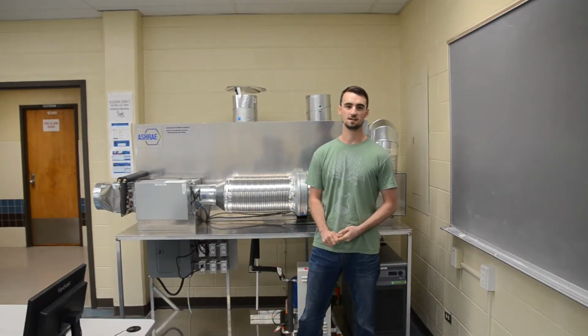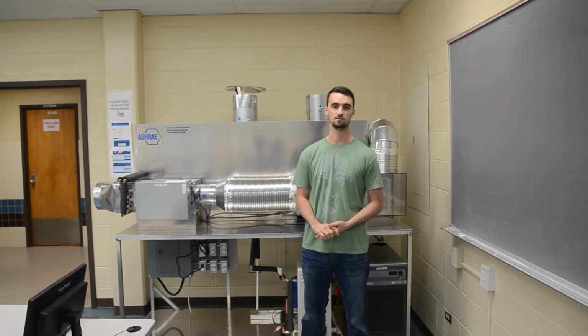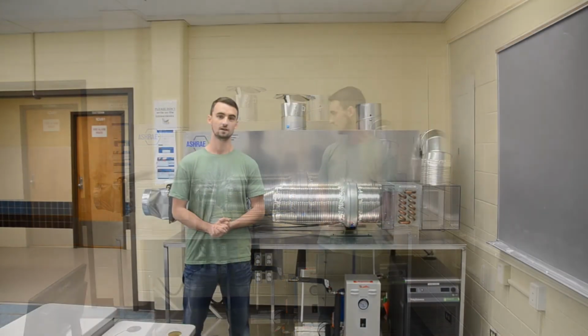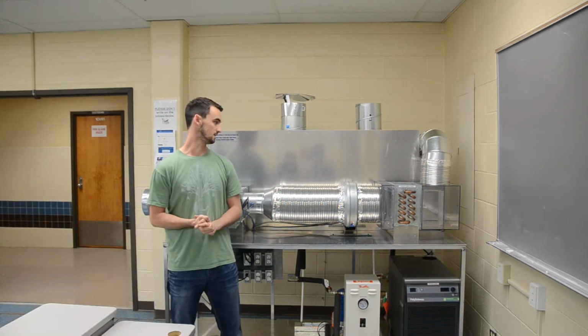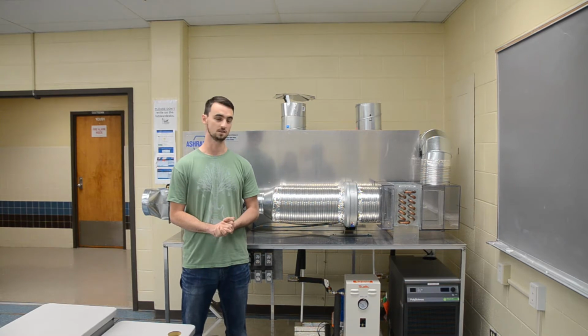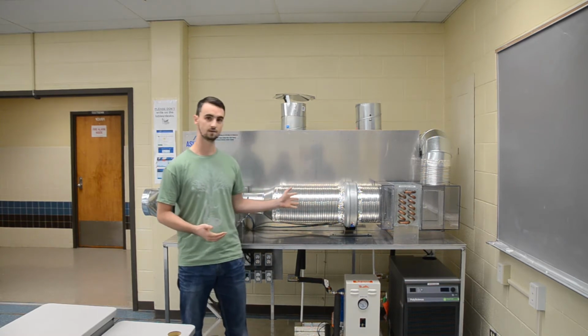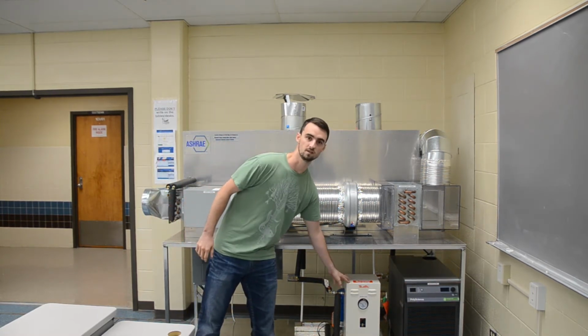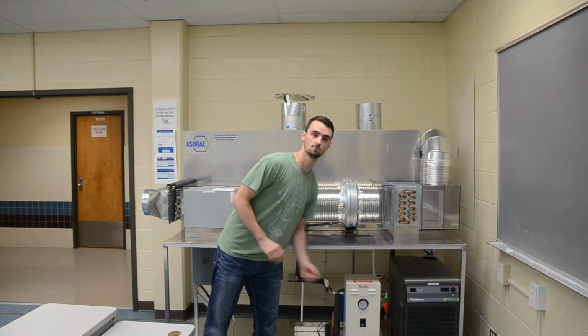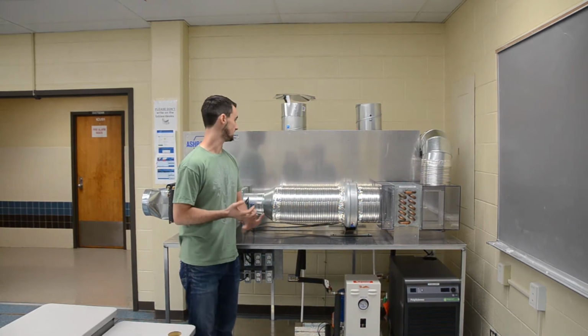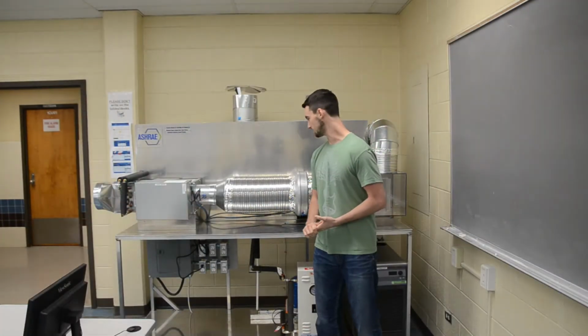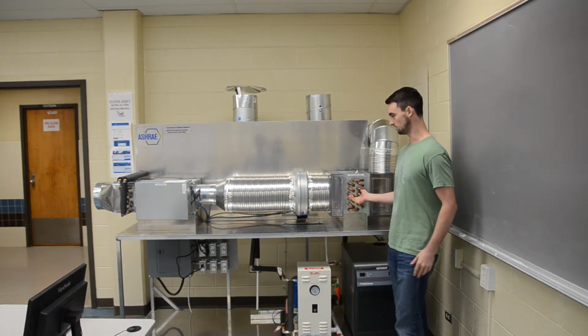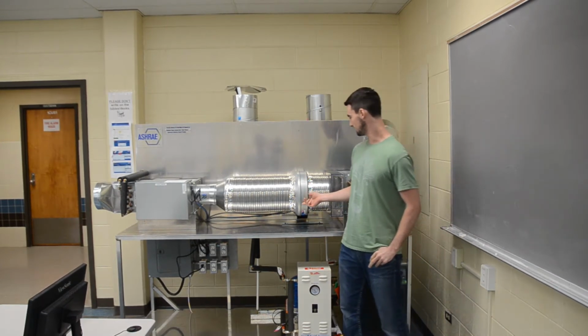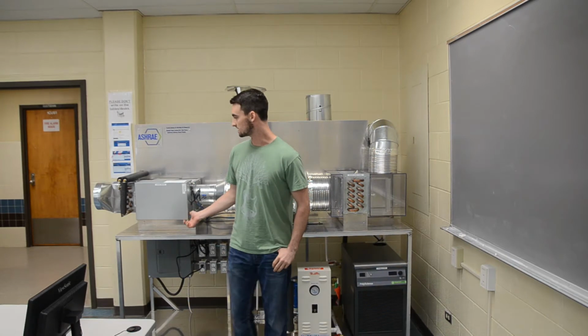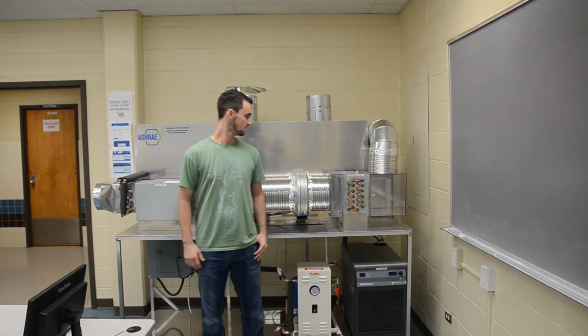Our system is a standard VAV system with the reheat coil, and it is meant to supply air to 2 zones. Our HVAC system has 4 different components, which is the supply air, the boiler in the hot water system, the chiller for the chilled water system, and the return ductwork. Right here you can see the cooling coil, fan, the VAV box, and the reheat coil system.